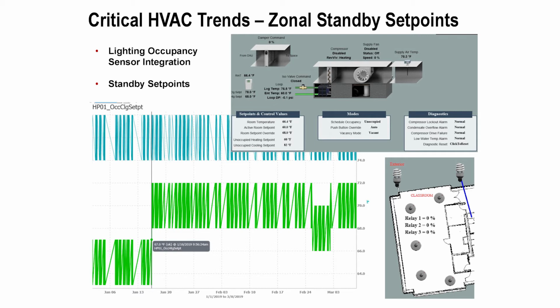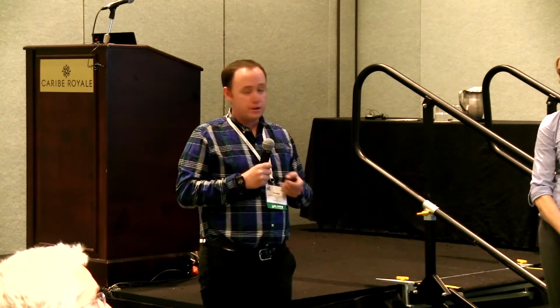I wanted to make sure we have this integrated system. It's always hard to get the lighting controls vendor to really talk with the BMS vendor. Sometimes there's only one individual in the lighting controls company who even knows how to do that interaction and integration. So this hung on for a bit after occupancy. It wasn't totally dialed in right away, but we had to make sure the lighting occupancy sensors were letting the HVAC system go to a standby temperature in the middle of the day.